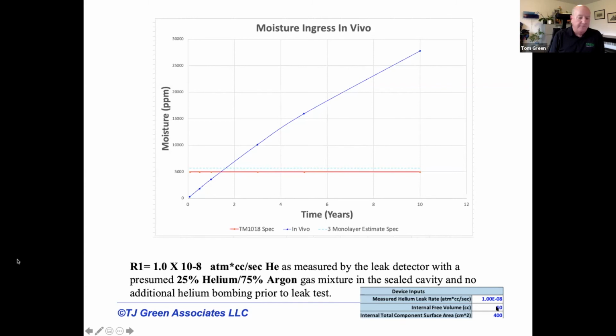And if the package volume was 10 cubic centimeters, and you started with no moisture to begin with, it's only a couple of years and you're beyond the 5,000 ppm mil spec. And then after 10 years, you're up into between 20 and 30,000 parts per million inside the device.